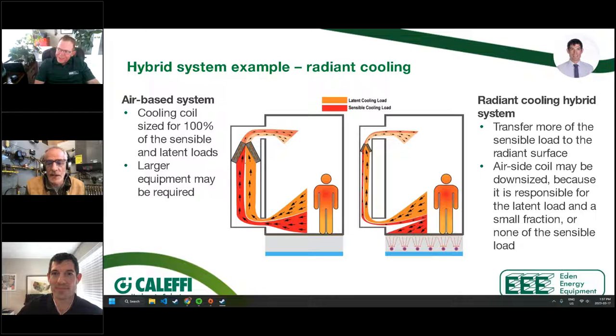Yeah, it's all about the loads. It starts with the math on the load numbers. But it's a dew point. Once you get temperatures down to where the air starts to sweat on everything, that's not going to be a very pleasant or acceptable condition. So you've got a very small window of what you can do with radiant surfaces. Maybe some of the ceiling stuff is a little bit better. I know some of those chilled beams actually have little pans under them, so if they do drip or sweat a little bit, they can collect that and get rid of it. But you don't want a wet, clammy floor. So you're going to be limited on the load that you can carry with that.